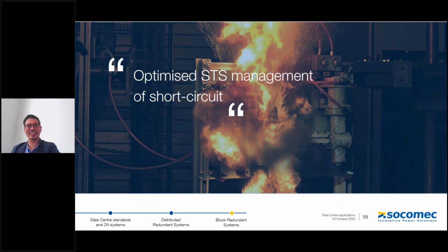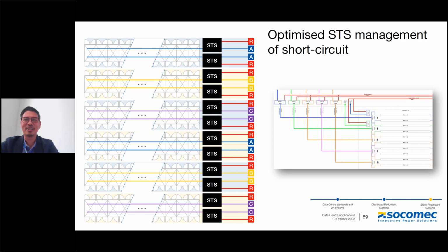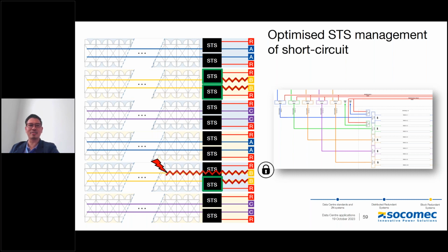Short circuit can go anywhere, from different distribution, and how that is managed should be managed by our STS. Different STS exist in the market, but in Socomec, this is how the STS will work: if there's any fault condition on the downstream, the STS should lock itself so that it will not propagate the fault to the other source. This ensures reliability and lets the fault clear either through the inverter of the UPS or the bypass channel. That's how an STS works in the system.